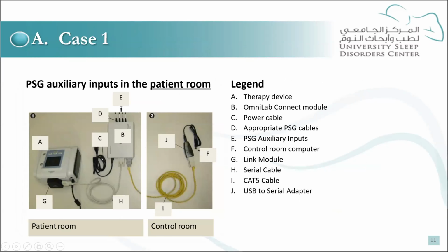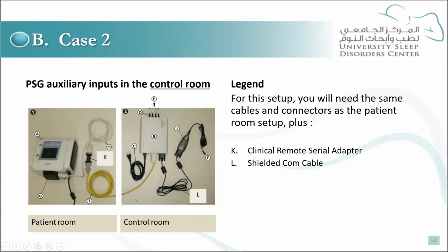So for case one, you can see the example here. On the left side, you have the patient room, and on the right side, you have the control room, the monitoring room. You can see that the box here is installed in the patient room, and you have the cables that are going to your polysomnography auxiliary inputs. The other setup, case two, is when your connecting box is placed in the control room, and then your polysomnography auxiliary inputs are placed in the control room, and then they go to your PSG system. So these are different setups.